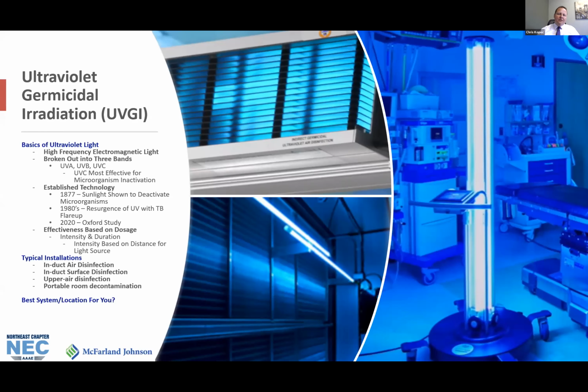Cost of this installation, a good rule of thumb, is about 50 cents per CFM for duct and air handling unit mounted UV systems. The bulbs are essentially the same as classic fluorescent tube lights and are typically rated for about 10,000 hours, so about a full year running 24/7 before they're degraded beyond effective range. Typically, the replacement bulbs run in the $10 to $20 range, depending on the length and the style and whatnot. Using the highest practical MERV filter in conjunction with the UV light is recommended, with a MERV 8 as an absolute minimum.